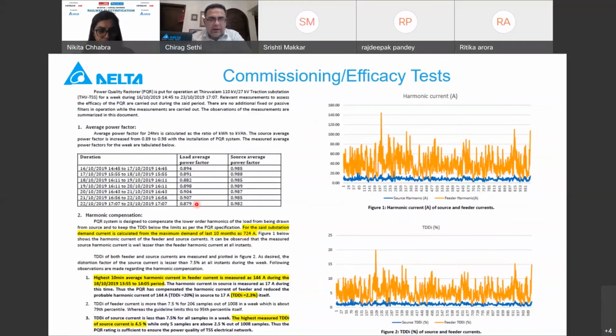Power factor without our equipment was in the range of 0.89, which was improved to close to 0.99. Secondly, with the maximum demand current of the TSS being 724 ampere, harmonic current used to be as high as 144 ampere, which is almost 20% TDD. After implementation of the system, this harmonic current was reduced to not more than 17 ampere at any time, both at a 3-second interval as well as a 10-minute interval. So the maximum TDD was 2.3%, which was within the limit.